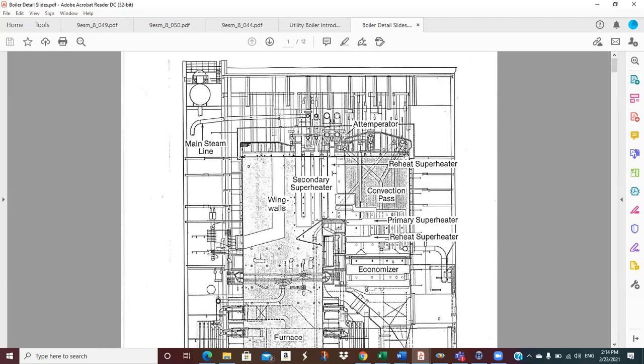We have attemperators, okay? And an attemperator is a steam temperature control device. What it does, it will spray liquid water or cooler steam into the steam path. And that steam is moving pretty fast through this thing. I mean, it's not sonic, but it's 500 feet per second. It's humming. And so you can very quickly adjust the temperature by spraying into the steam. And you don't do it as the steam leaves, because you're afraid that the attemperator, if it's blowing water, could blow a bunch of water in there, and that water not evaporate before it got to the turbine, and then you'd slug your turbine with water. So they always do it in between.